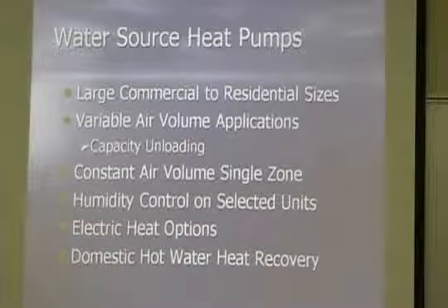So the reason for electric heat is to supplement that heat, because with normal heat absorption water temperatures you can generate enough heat out of the compressor, but when your water temperature is very cold, your air delta T goes down. Domestic heat recovery is another little heat exchanger, a refrigerant to water heat exchanger built into the heat pump, where you run your domestic water out of your storage tank, through the heat exchanger and back into your storage tank. You have to put a little separate circulating pump on your domestic water to draw it out of your storage tank and put it back in your storage tank. But then when the unit is on, it delivers hot gas to that heat exchanger so that you're actually getting a little bit more energy efficiency out of the heat pump. You're using that domestic water heat exchanger to absorb some of the heat in the system.